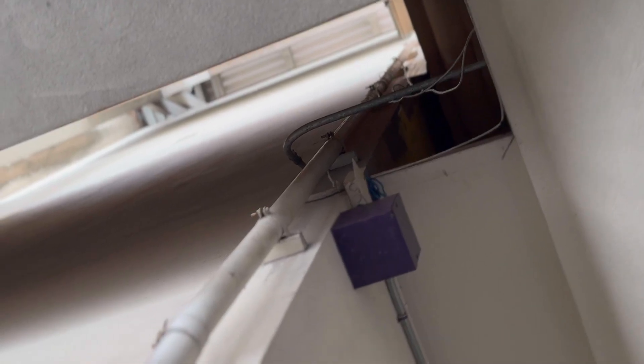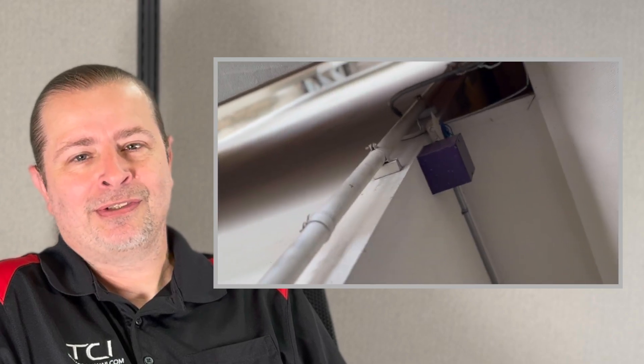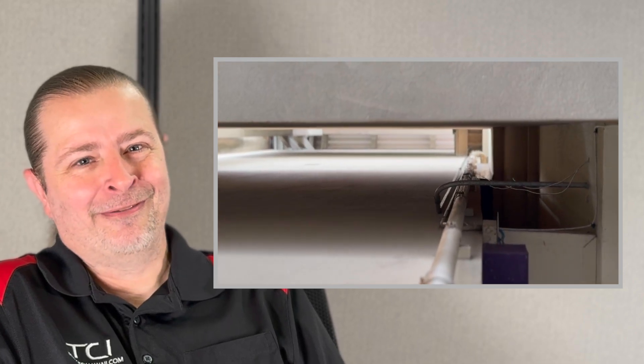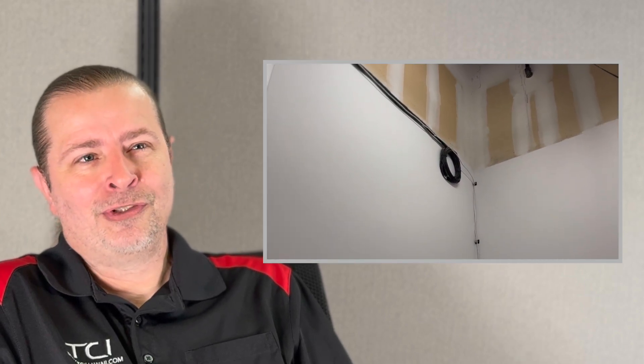It turns out this wire ran upstairs to a closet on another floor entirely, and that's where the telecom services were. It was a shortcut the installer took to get done quicker. Why don't you do this? Well, it's working, right? But that's an interior cable that's exposed to rain, sunlight, and vandalism. People do steal copper — they'll grab it right off the wall. There's so much about this that's obviously wrong, but in the interest of saving time, people take some pretty interesting shortcuts.